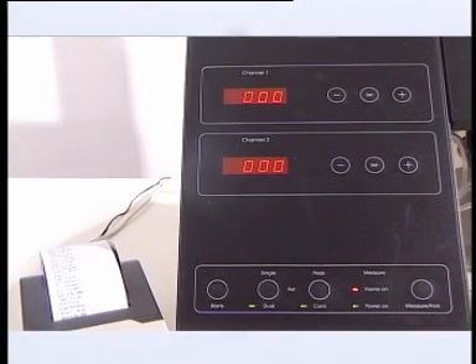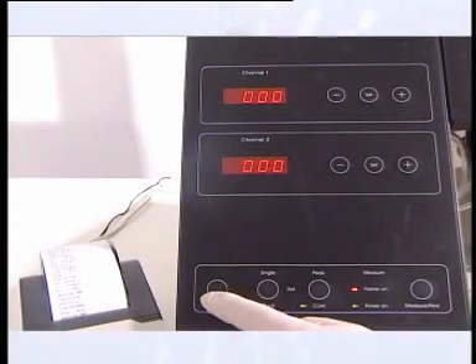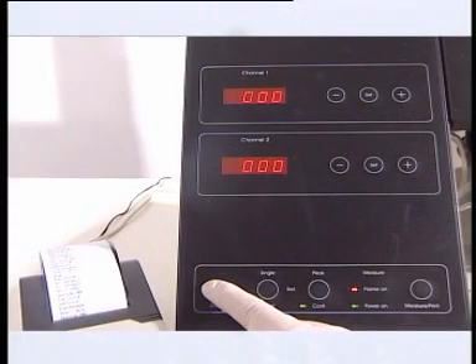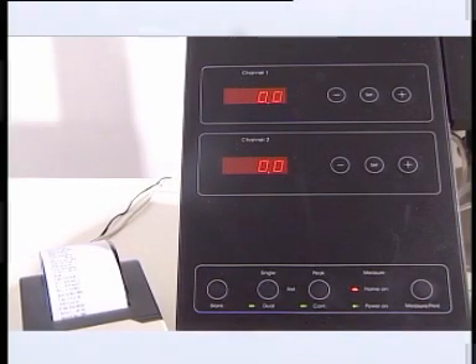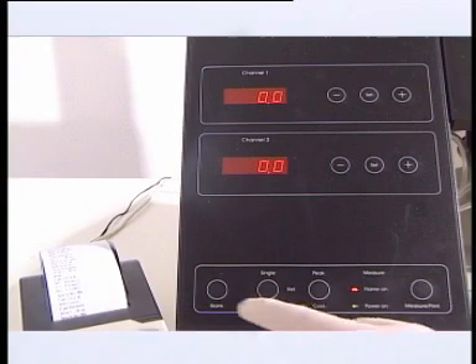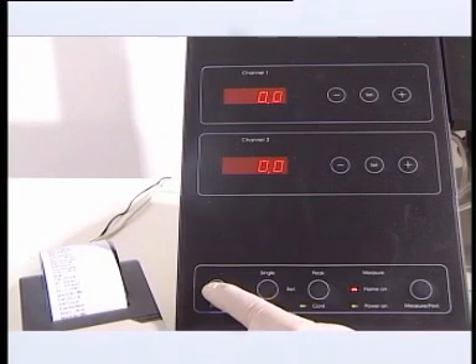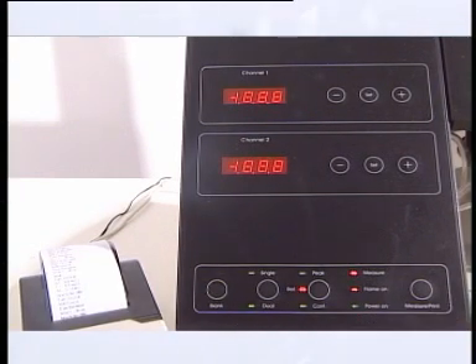If during a measurement it is necessary to reset the blank when aspirating the blank solution, the blank button can be pushed momentarily. This will reset the 0 point of the system and the instrument will then revert to the measure mode. If the blank button is held down until it bleeps, then the system will reset and the blank and calibration will be needed.